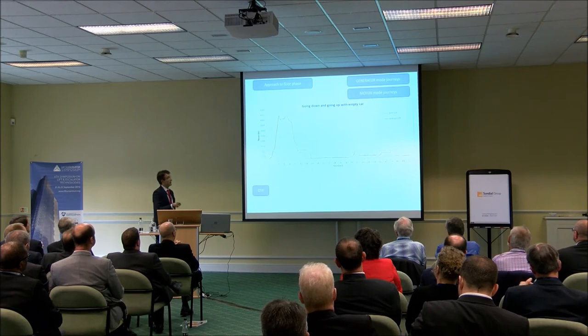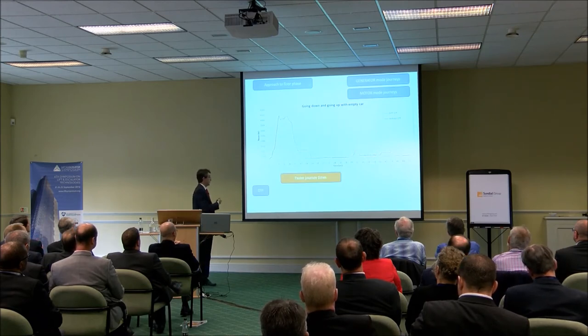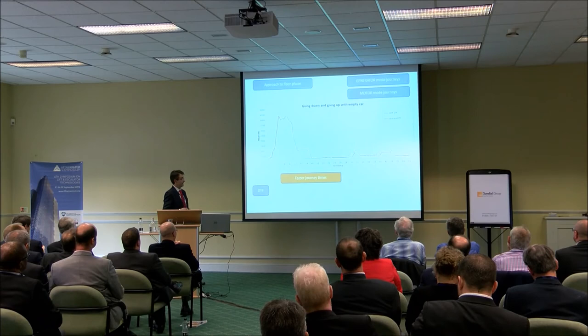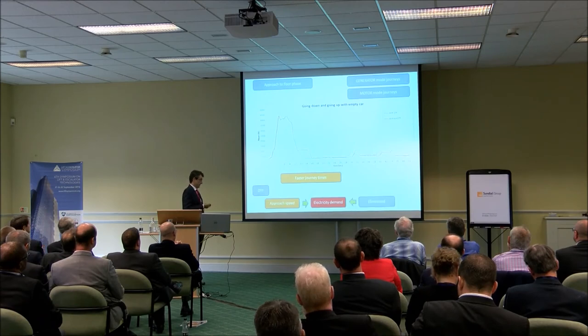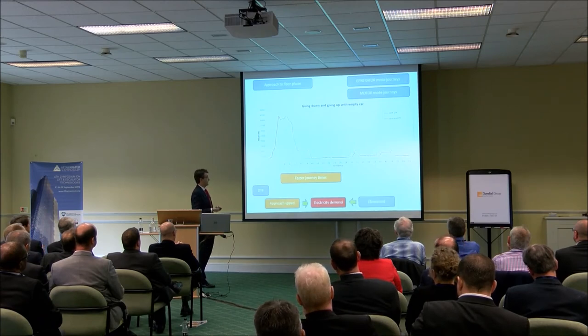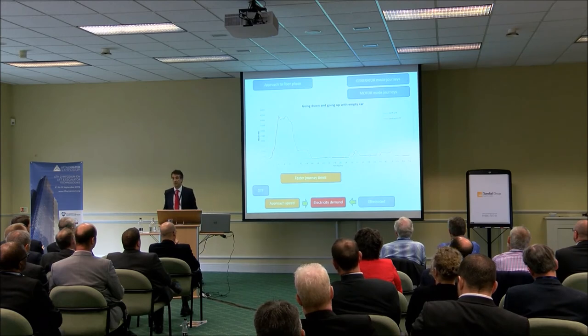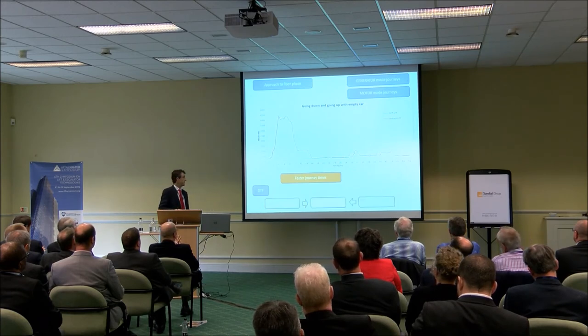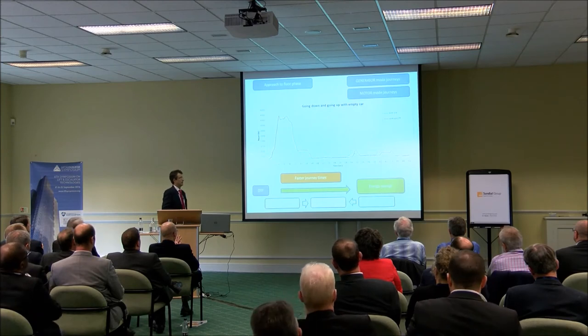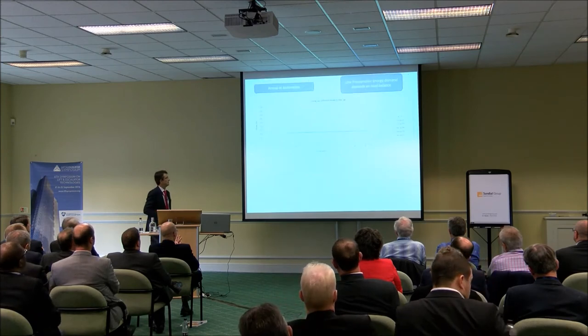The next phase is approach to floor. We know that direct-to-floor solutions achieve faster journey times. Approach speed always generates electricity demand, so direct-to-floor solutions eliminate the approach speed phase, helping to achieve energy savings.